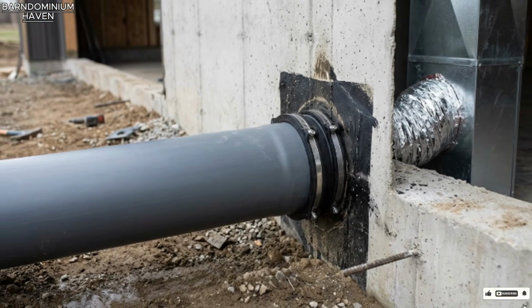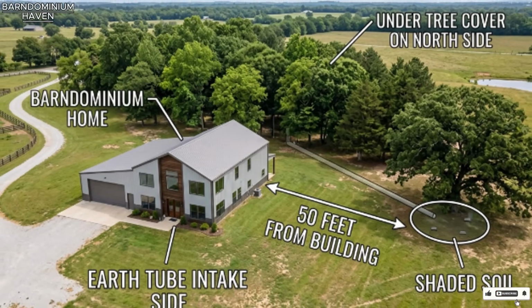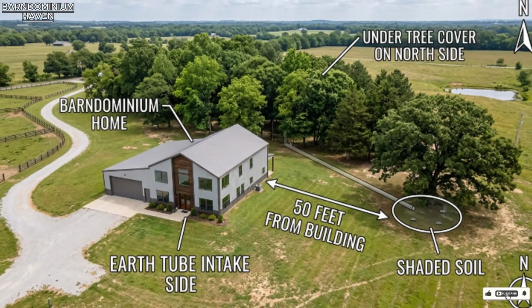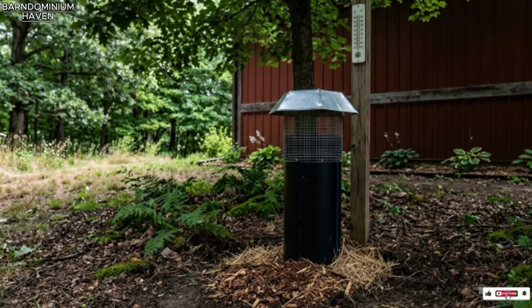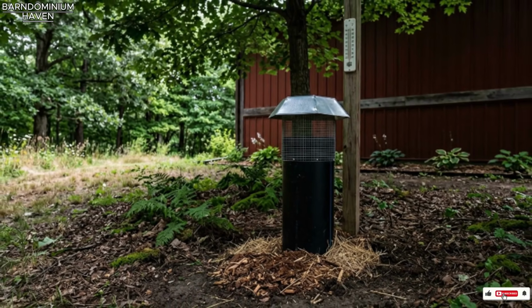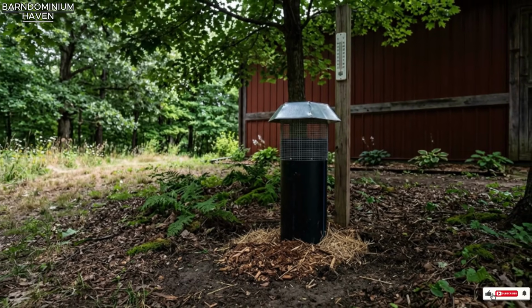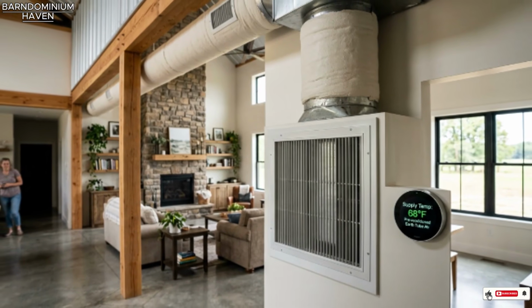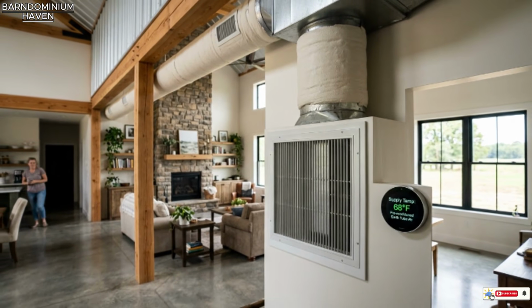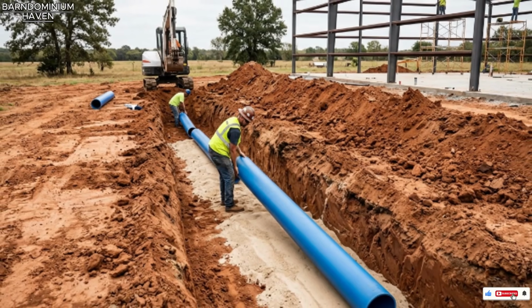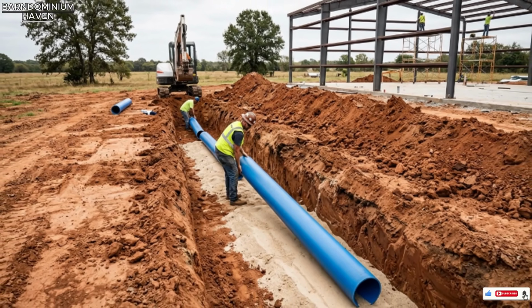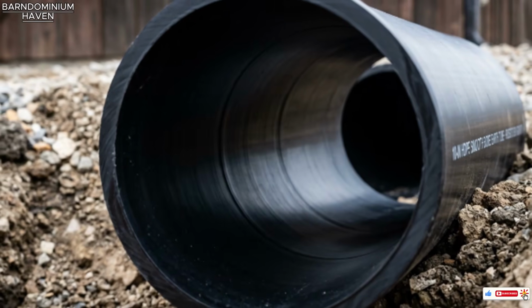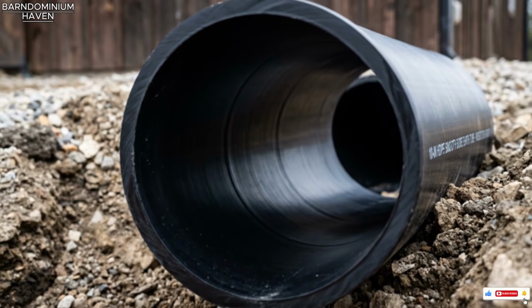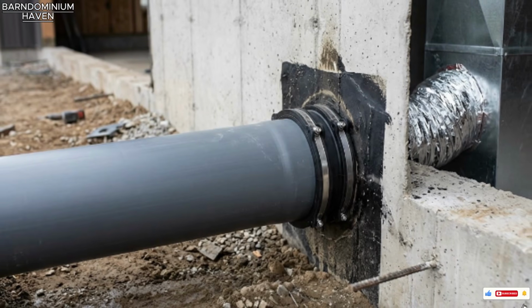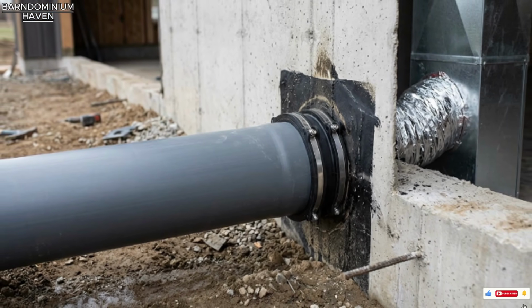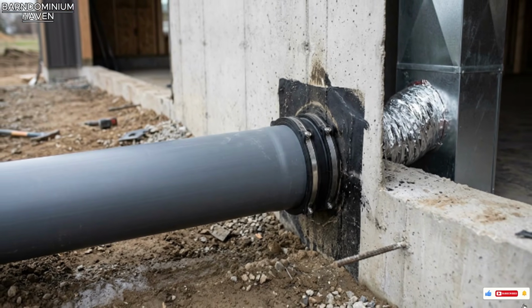The intake location, the point where outdoor air enters the earth tube system, should be a minimum of 50 feet from the building's foundation, and ideally located in a shaded area, under tree cover or on the north side of a feature that prevents direct solar radiation on the soil surface above the pipe, which further reduces the ground temperature at the pipe's depth and improves the system's cooling performance. In a barndominium whose site plan was designed to accommodate the earth tube run, the pipe is laid in a trench dug before the driveway is poured, before the landscaping is established, before the site work is complete, and integrated into the building's mechanical rough-in at the foundation stage, connecting to the building's air distribution system at a single intake point in the foundation wall or through the slab.